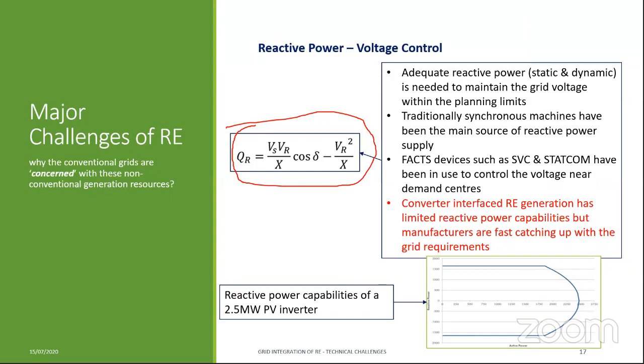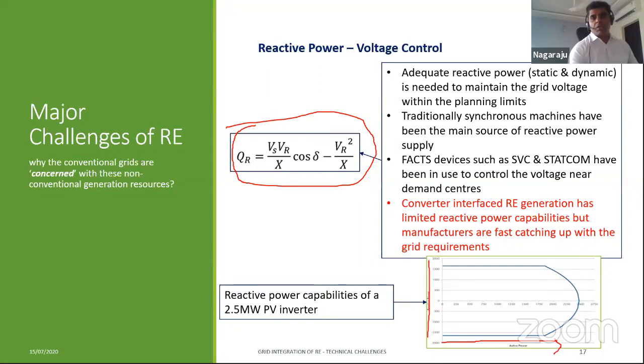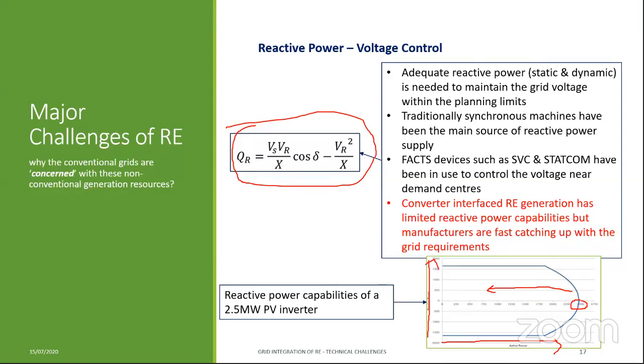But the converter interface machines do have some limited capabilities. Manufacturers are now coming up. You can see the bottom picture shows the reactive power capabilities of a 2.5 megawatt PV inverter. What we are seeing here is the x-axis is the active power, and the y-axis is the reactive power. When the machine is running at full rated active power, we will not get any reactive power. Reactive power is 0, whereas a lot of grid codes do ask for some reactive power output when the machine is running at its rated power. When the machines are running at less active power output, they can provide a lot of reactive power support, but grid requirements are challenging here.